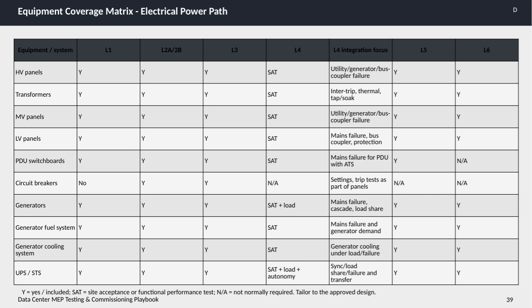We can see that most equipment undergoes testing at levels L1, L2A/2B, and L3, with site acceptance tests or functional performance tests indicated at L4. For example, HV panels, transformers, and MV panels all require these SATs. The specific focus at L4 often includes scenarios like utility or generator failures, intertrip protection, thermal issues, and tap or soak tests. Circuit breakers are an exception, typically starting at L2 testing and focusing on settings and trip tests as part of panel testing.